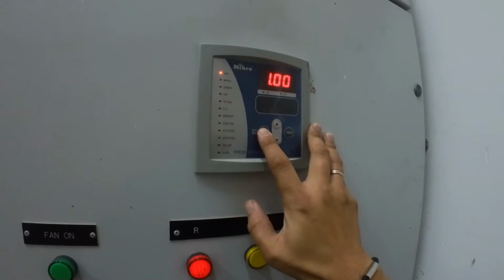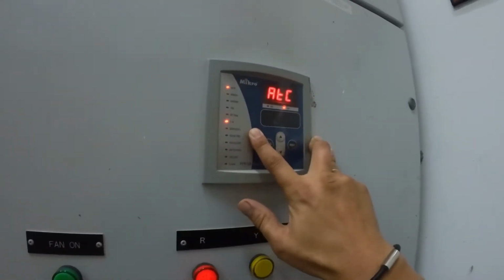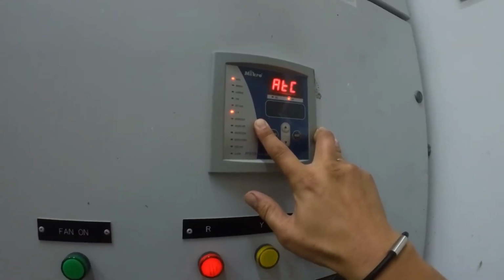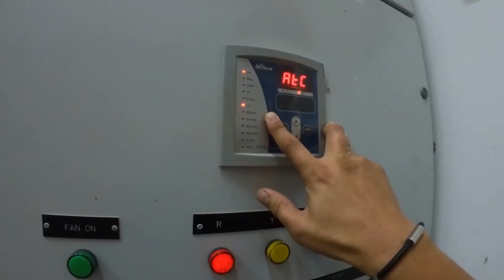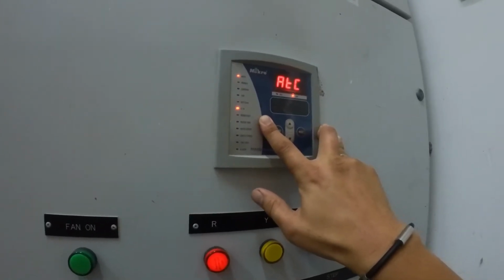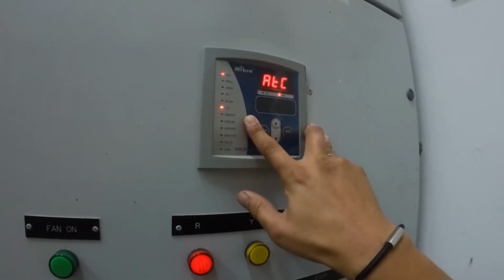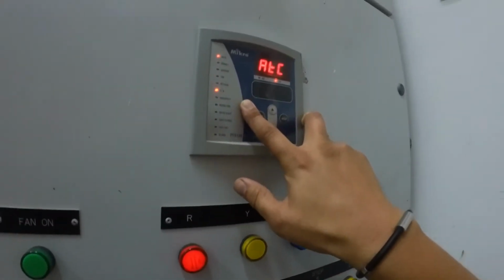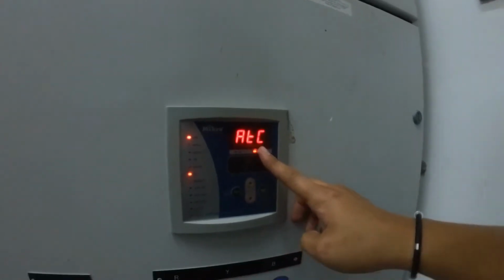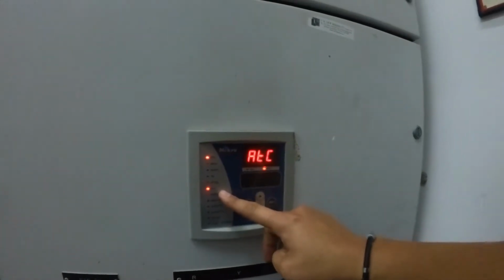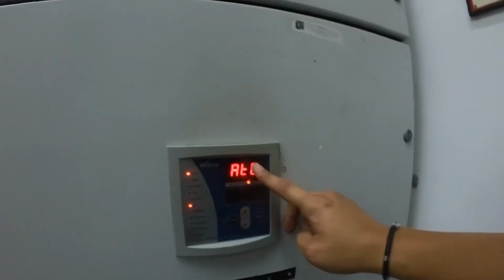So press program. Next we have the CK value. The CK value is much more applicable if, let's say, you have a big installation and you have a CT of 2000 or 3000/5. Then you want the cap bank to be more precise and accurate without overcompensation, so you can set the CK value. Here we use the ATC, which means it isn't based on the CT loading factor. It's only based on the power factor value.